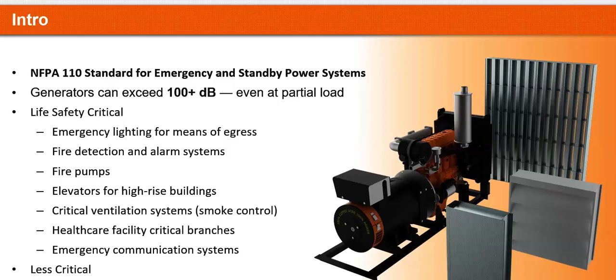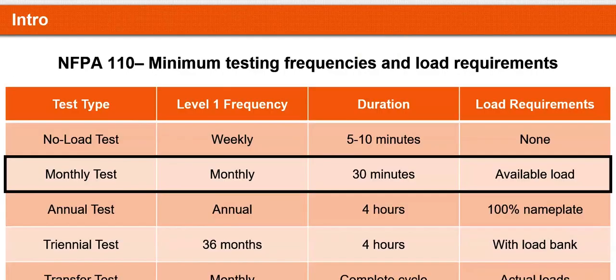NFPA 110 is the code that establishes requirements for performance on these generators, but as it relates to noise control, it sets the minimum testing frequency for these units. So in any schools, you have emergency generators, airports, police facilities, military facilities, and when you turn them on for testing, they can be extremely detrimental to human hearing. Although the minimum requirement for testing frequency under NFPA 110 is only to test them once a month for 30 minutes at available load, depending on the jurisdiction and the environment, these are tested a lot more often than just that.